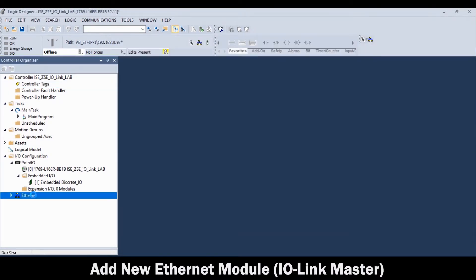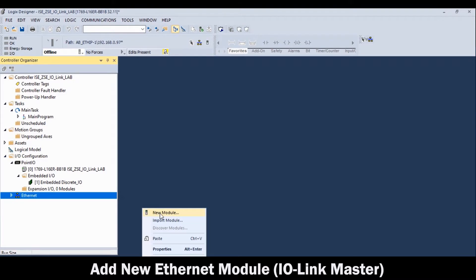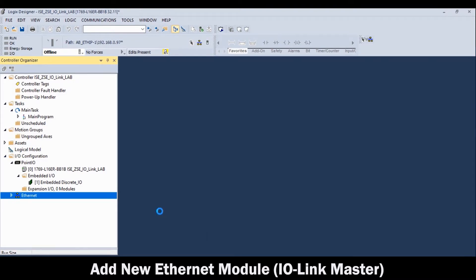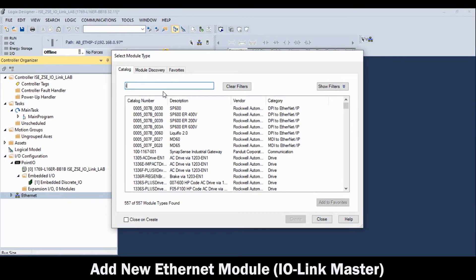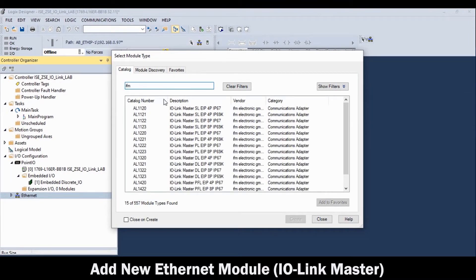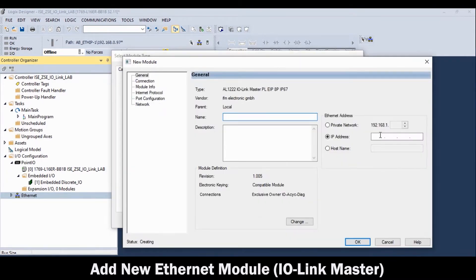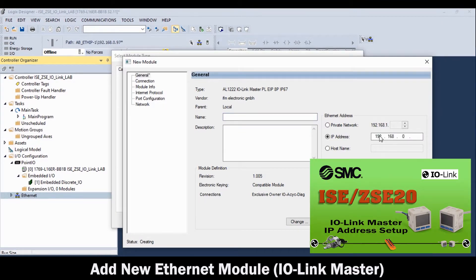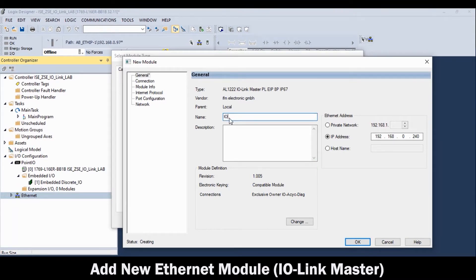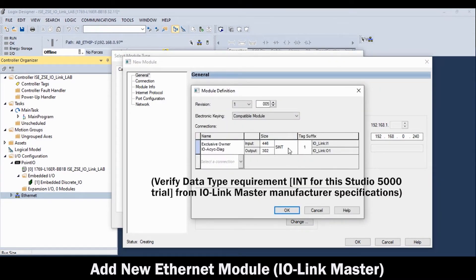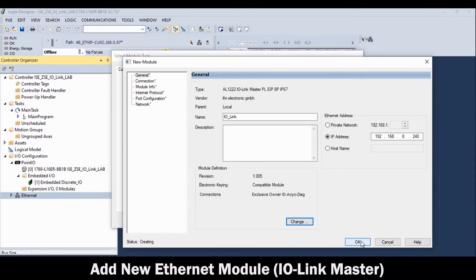Right-click on the Ethernet scanner in the controller organizer and select New Module. Isolate and select the commercial IO-Link master brand. Then, in the Select Module Type table, highlight the IO-Link master model and click Create. In the New Module table, enter the IP address previously set for the unit. Then, enter the desired unit name. Before moving on, click Change, then change the data type to Integer. Then click OK.